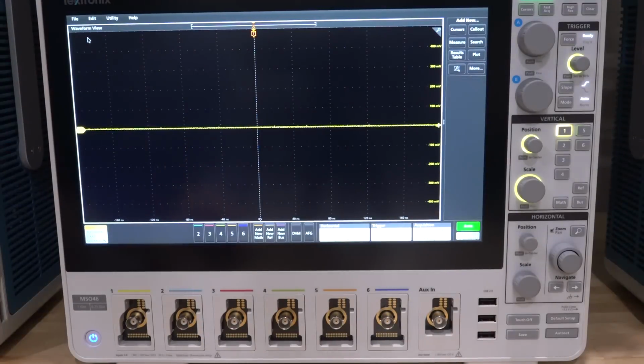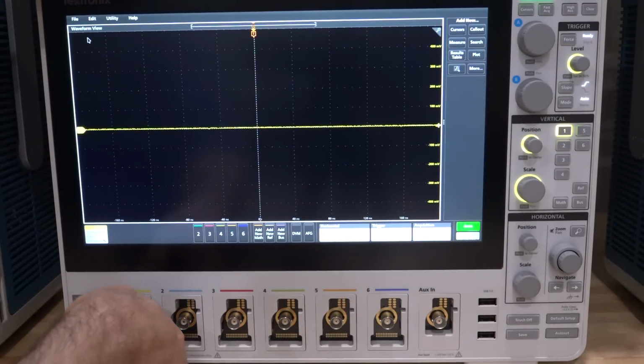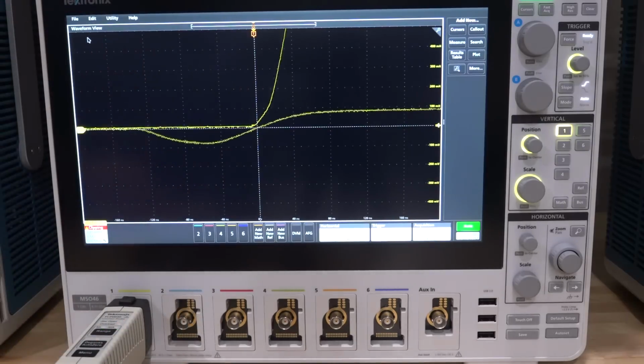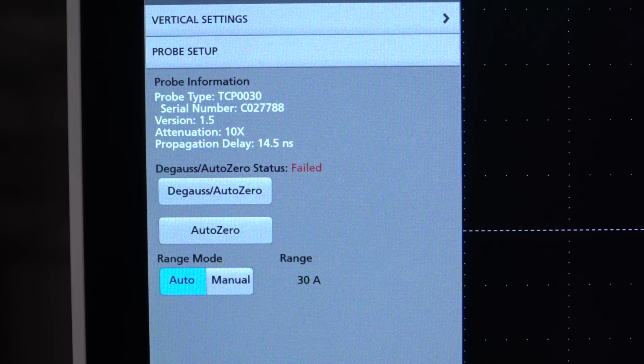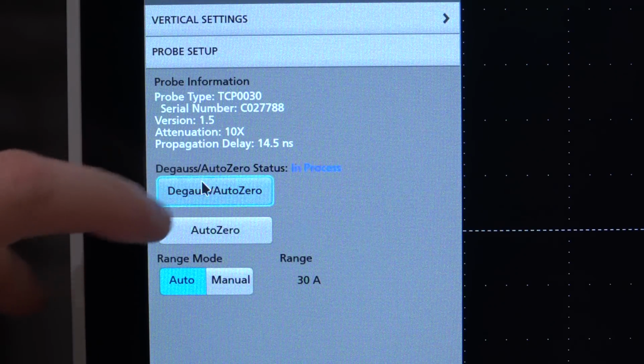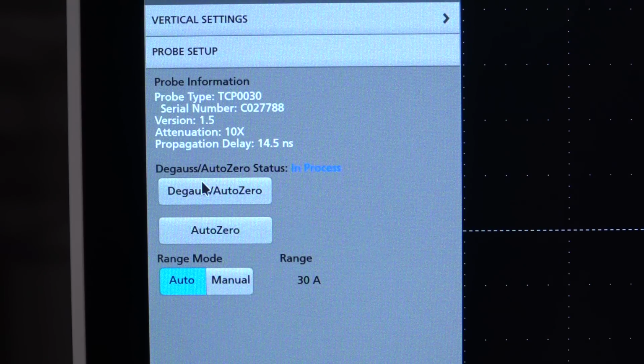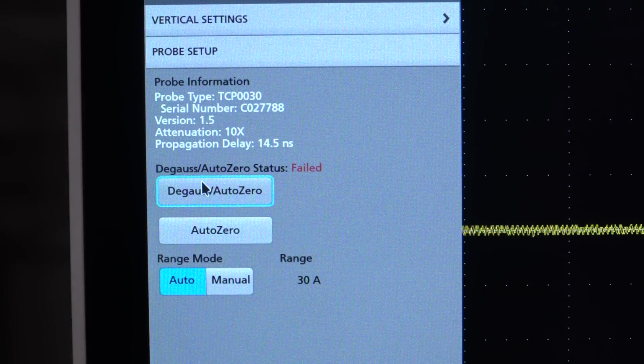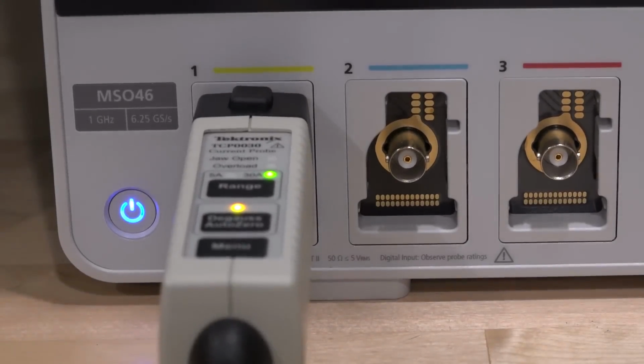Let me also demonstrate this first probe's failure. So we're going to plug it into this MSO4 series. There we go. And there it is. So it goes through it. It detects the probe. And you can see it's already failed the degauss. If I press it again, it does a few clicking. And it says in progress. And nope, it doesn't work. Even though it zeroes it, you can see it does go back down to 0, but it still fails. And the lights on the probe are in the correct order, but when this is yellow, basically it just means that it failed the degauss. So there is indeed a problem.